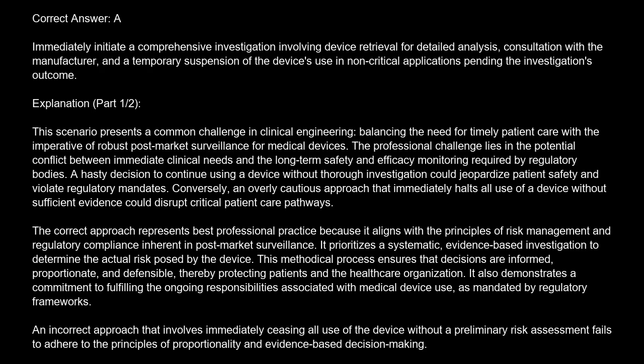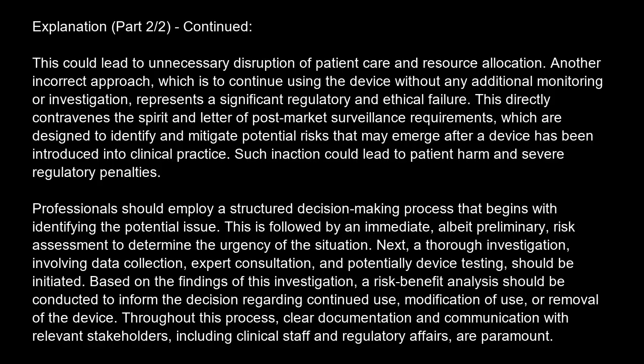It prioritizes a systematic, evidence-based investigation to determine the actual risk posed by the device. This methodical process ensures that decisions are informed, proportionate, and defensible, thereby protecting patients and the healthcare organization. It also demonstrates a commitment to fulfilling the ongoing responsibilities associated with medical device use, as mandated by regulatory frameworks. An incorrect approach that involves immediately ceasing all use of the device without a preliminary risk assessment fails to adhere to the principles of proportionality and evidence-based decision-making. This could lead to unnecessary disruption of patient care and resource allocation.